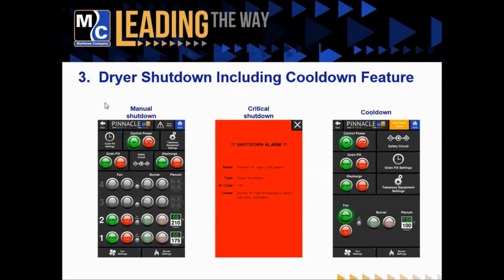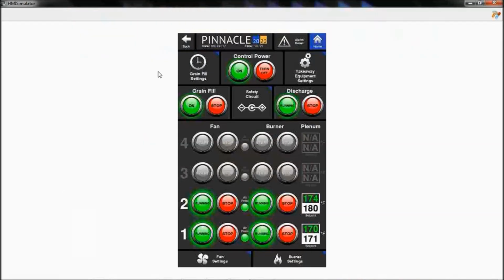So once you've run your dryer for several hours and you're ready to shut down, there's a couple different ways that the dryer could be turned off. It'll either be shut down by your decision to shut down the dryer, or due to a critical or cool down alarm. So we're going to go through each one of those scenarios and explain how the dryer is shut down in each case. So if there's no alarms, you're just done drying for the day and you'd like to shut down the dryer, we'll go through a manual shutdown.